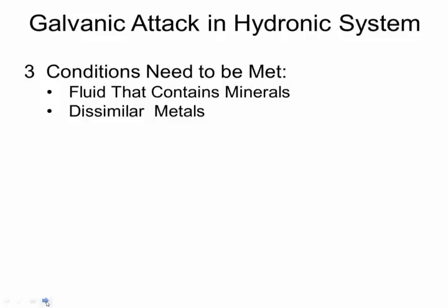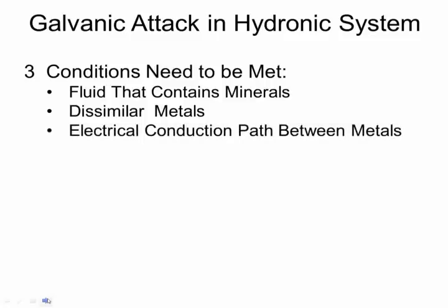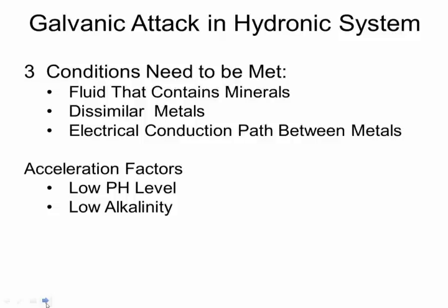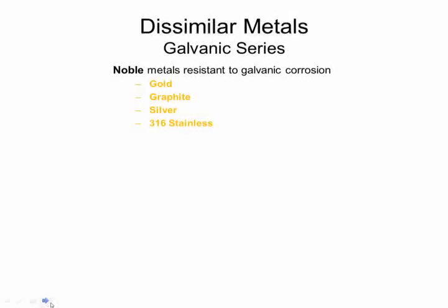Also, your hydronic system needs to have dissimilar metals on the galvanic chart. So if your system is largely copper piping and you have a copper tube boiler and everything else is metals very similar to copper, you won't have an issue. And the last thing you need is an electrical conduction path between your metals. Your metals need to be joined, okay? It's much like your car battery. Between the positive post and the negative post is the potential, right? But nothing happens until you turn the ignition in terms of electron flow. The same holds in a hydronic system. Acceleration factors: in this case, galvanic attack acceleration happens as a result of having low pH and low alkalinity, or both, okay? So those determine the rate of a galvanic attack.